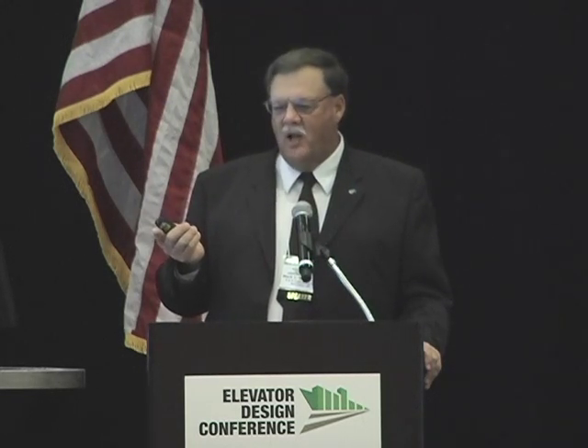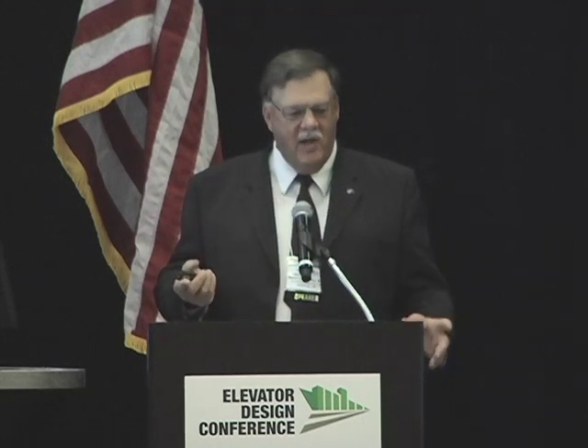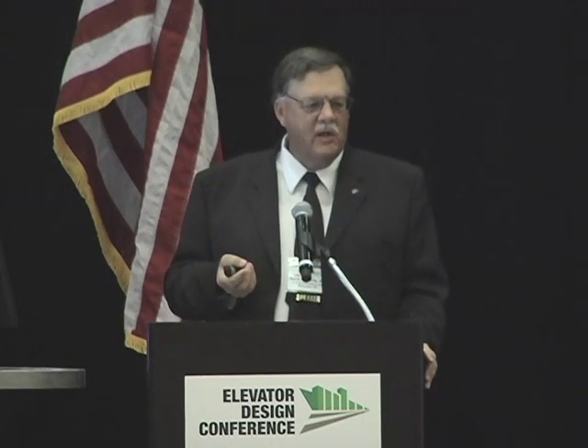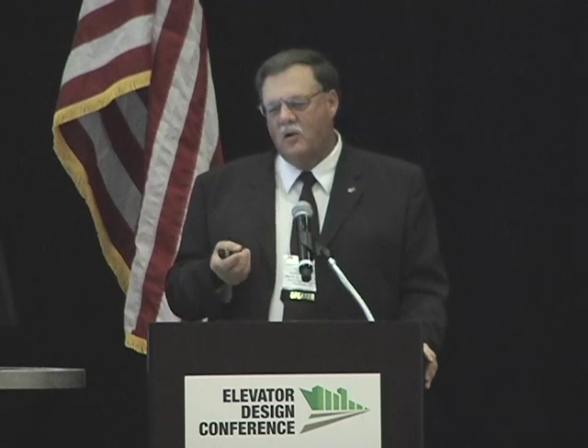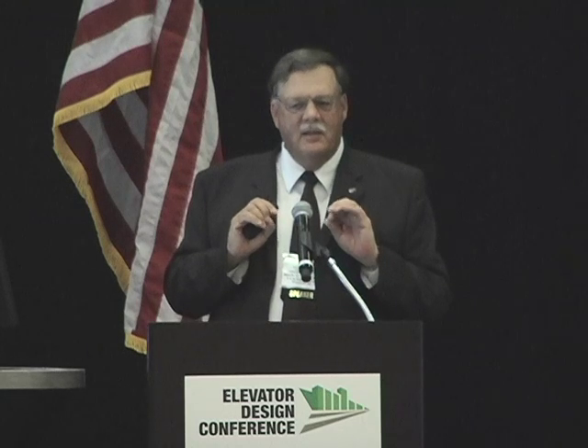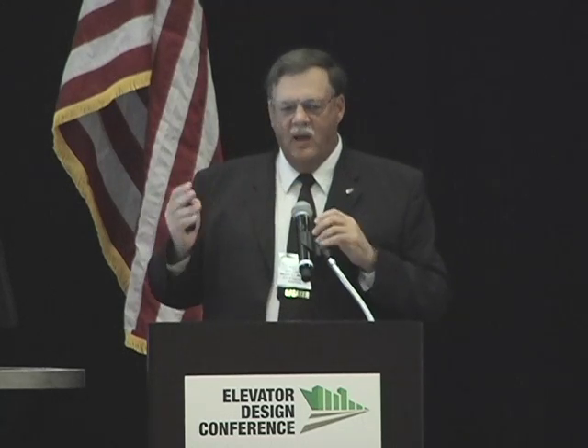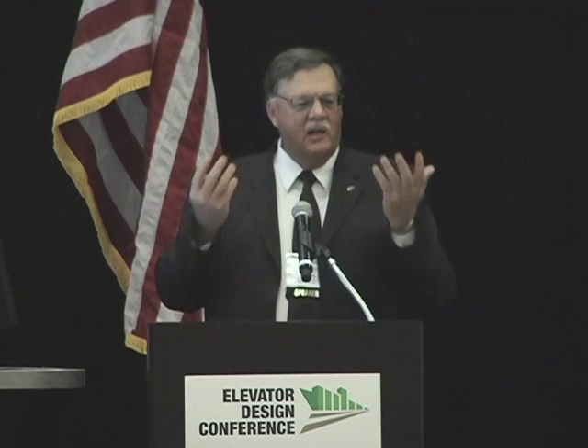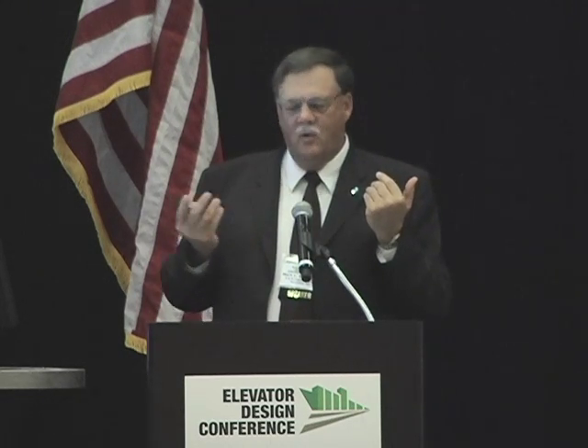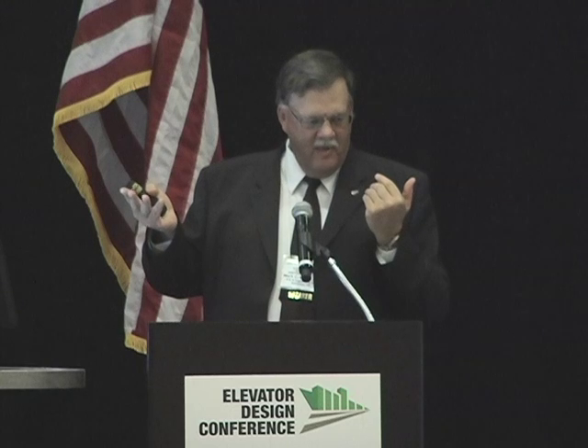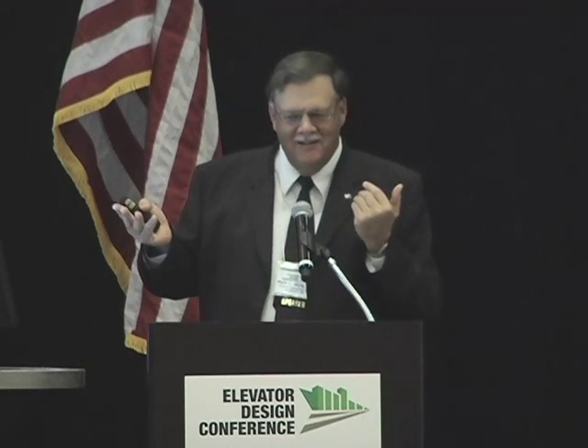So that if there is an arc flash event within the equipment, it directs all the arcing up through a venting system through the top of the equipment and takes it away from the people working on it. The breaker compartments are compartmentalized and isolated, and a lot of things are done to keep that arc flash from coming out of the front of the equipment and take it up the top. Now, you do have to be concerned about what's above that equipment when you do this, because you don't want to start your building on fire when the arc flash goes out the top.